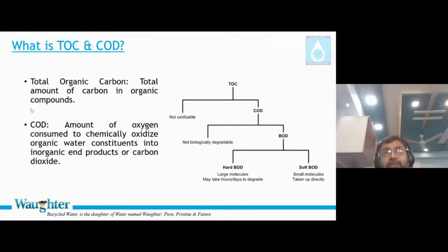So amongst BOD, which is typically termed rbCOD, what is the meaning of soft BOD and what is the meaning of hard BOD? Let me explain to you. For example, you have sugar in your waste. Sugar is very easy. Bugs will love it, right? It is readily hydrolyzed and they immediately start consuming it. So the right term for soft BOD is RBCOD, readily biodegradable COD. And some large molecules or even particulate molecules will take more time to hydrolyze. For example, my saliva. These kinds of things take a little more time to hydrolyze first and then be available for bacteria to intake, and then we start calling them hard COD.